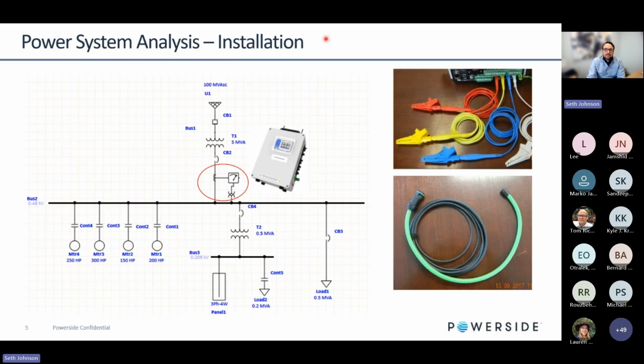So where do we like to install this device? Here I've got an image of a PQube. This is just a basic single line diagram that we put together. And the idea here is you got your transformer and then your main breaker that's feeding the facility. And ideally, if there's nothing tapped off the transformer, we like to be on that secondary side of that main breaker, or sometimes in the main transformer, depending on the configuration. And this is so that we're able to see the full load and the full system.